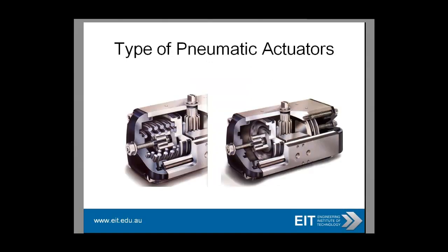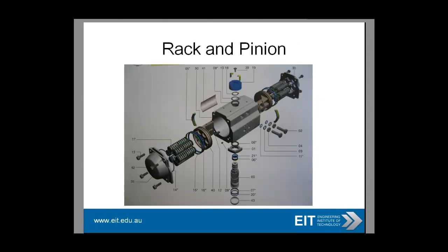Rack and pinion actuators give a constant high torque, have minimum hysteresis losses, their stroking speed is relatively high, and they are easy to assemble and maintain. You can see where the rack and pinion comes in on the inside — as that rotates, it operates the valve. It does not work well with dirty or moist air because those little O-rings get damaged very easily, so you have to protect them at all times. The O-rings are marked in blue and green on the screen.